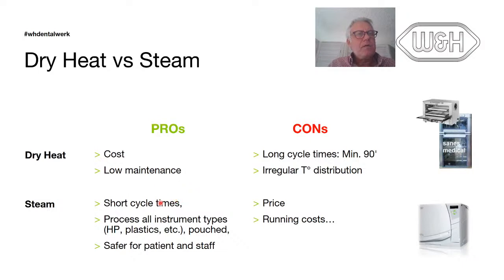With steam, the cycles are quite short. It's around 30 to 45, 50 minutes. It can process all instruments. I cannot think of one instrument that you use in the mouth that cannot be processed in a steam sterilizer. Okay, some X-ray sensors, some very specific items, but otherwise you can sterilize plastic, rubber, everything, and you can sterilize them pouched, which you cannot do with a dry heat sterilizer. You cannot pouch because this will again prevent heat from reaching the instrument.